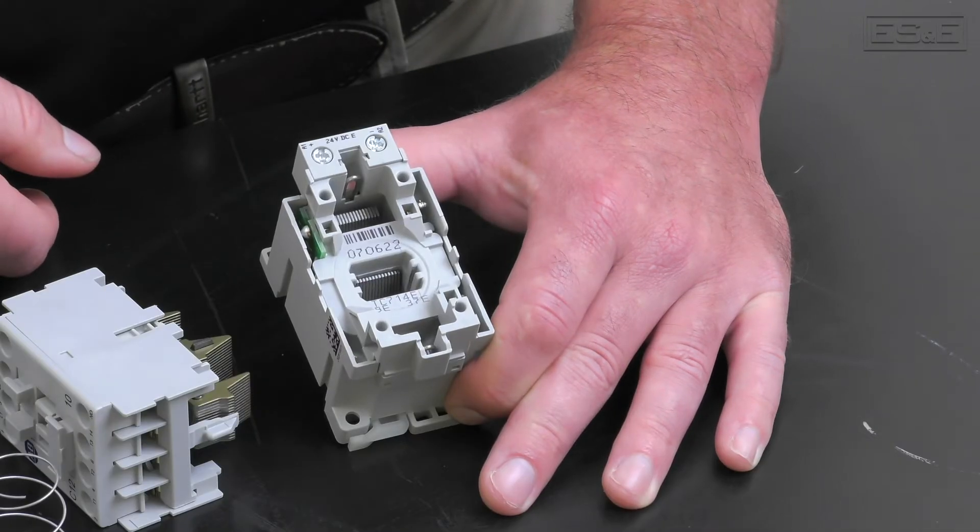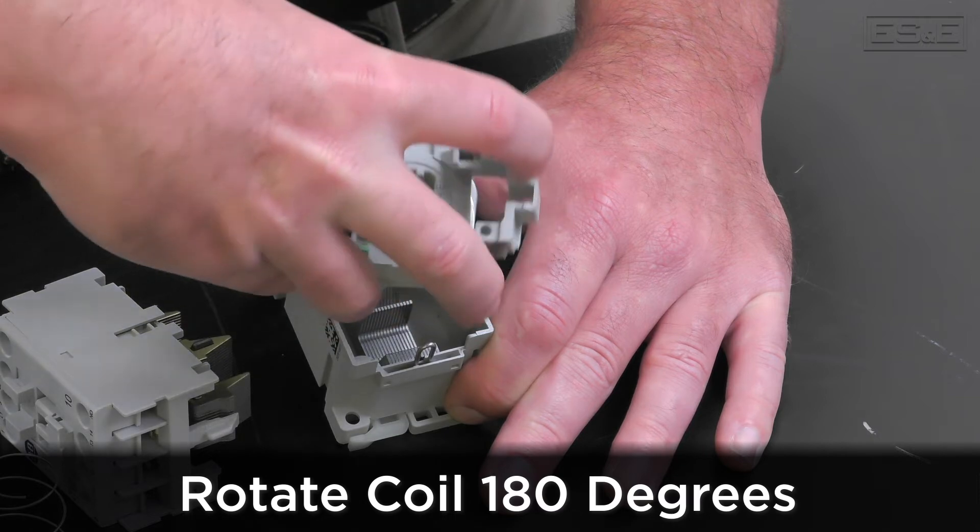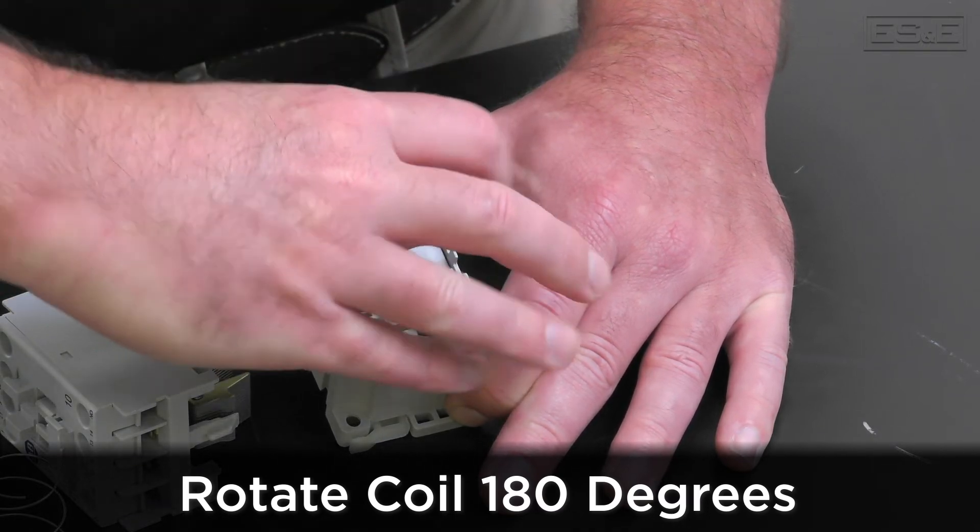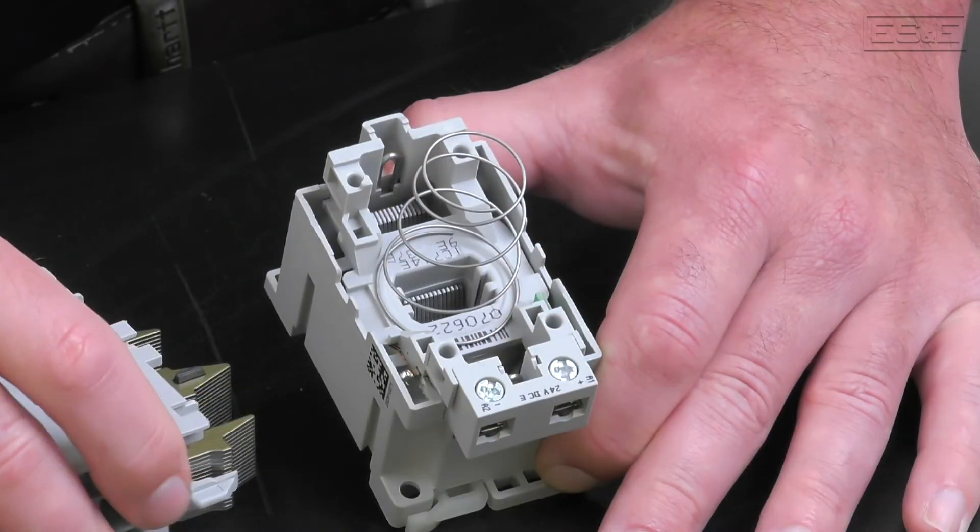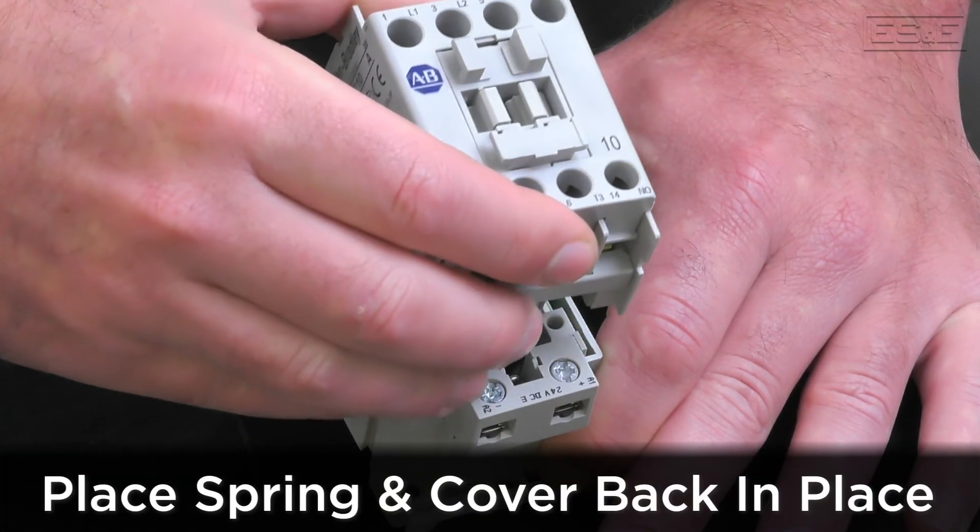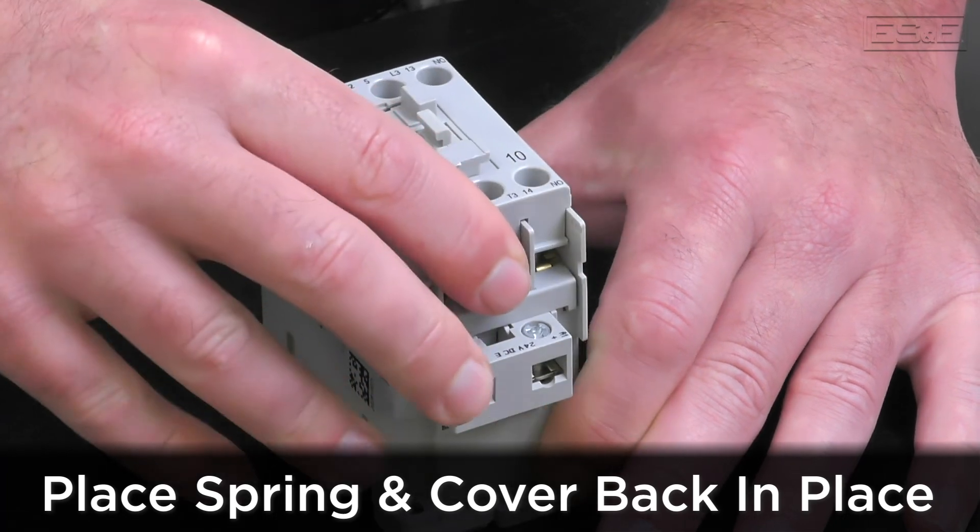If you are rotating the coil, rotate it 180 degrees so that the terminals are facing the opposite side of the contactor. Then place it back down into the contactor base. Once the coil is properly seated, you can place the spring back on top and then replace the cover.